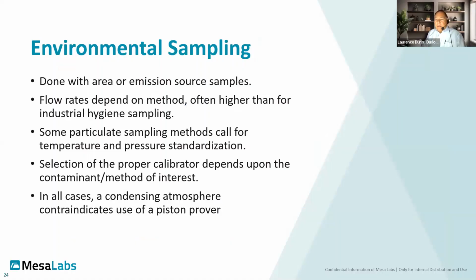Environmental sampling is a little bit different, conceptually very similar in terms of the sampling media. The equipment is a little bit different, typically a higher flow rate, which means it's larger equipment that's not personal-compatible, line powered in many cases, but typically higher than industrial hygiene sampling. Some of their particulate methods require standardization, some don't. You'll have to look at the method itself to determine which it is. The calibrator that we use depends on the method of interest, because the typical low and medium flow industrial hygiene calibrators may not work. You may have to use a high flow device.